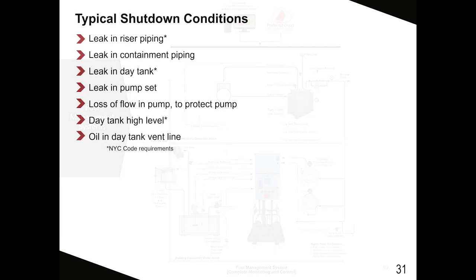Correct. These are typical shutdown conditions we recommend. Leak in a riser, leak in containment piping, leak in a day tank, leak in a pump set, loss of flow in a pump to protect the pump, day tank high level, and oil in the vent line. The asterisk, the leak in the riser, leak in a day tank, and day tank high level are code required shutdowns in New York City.